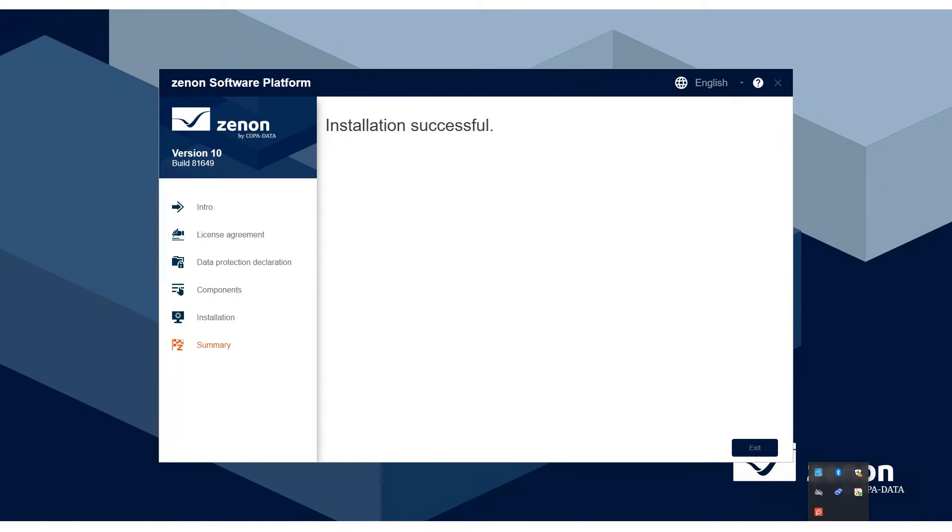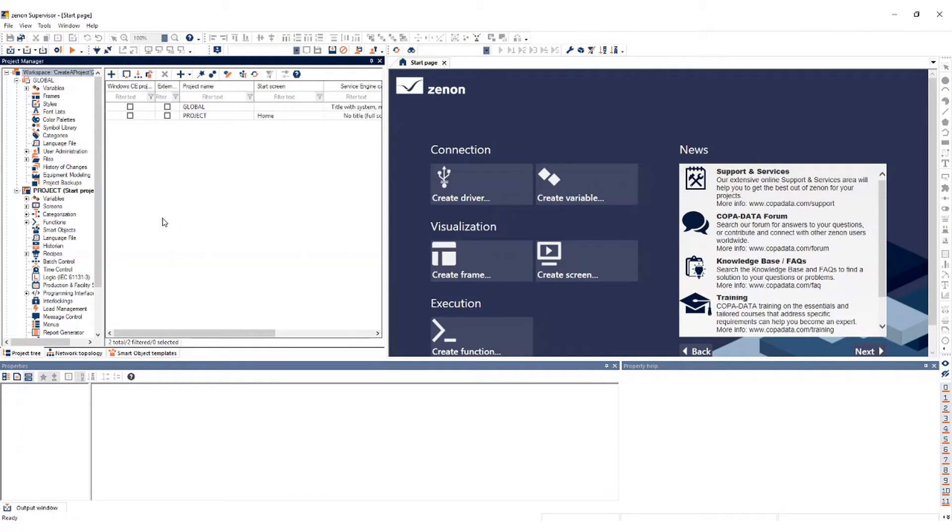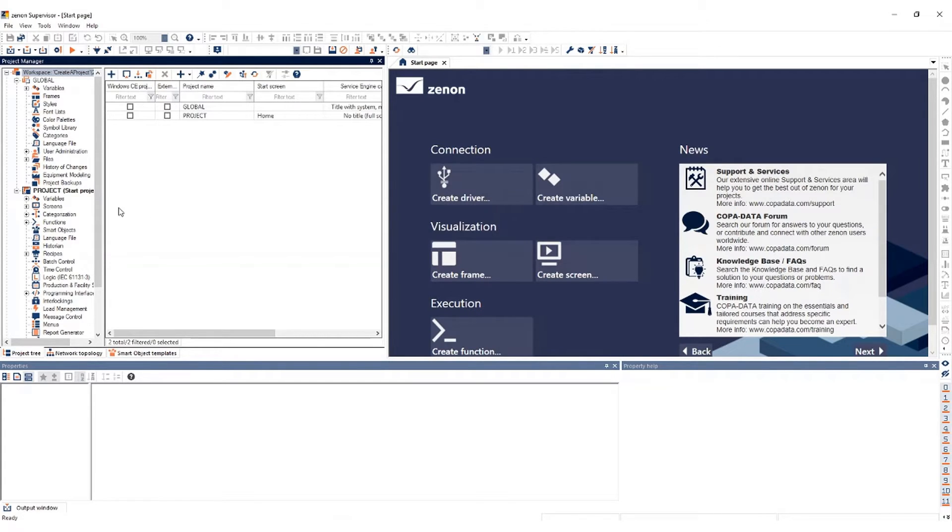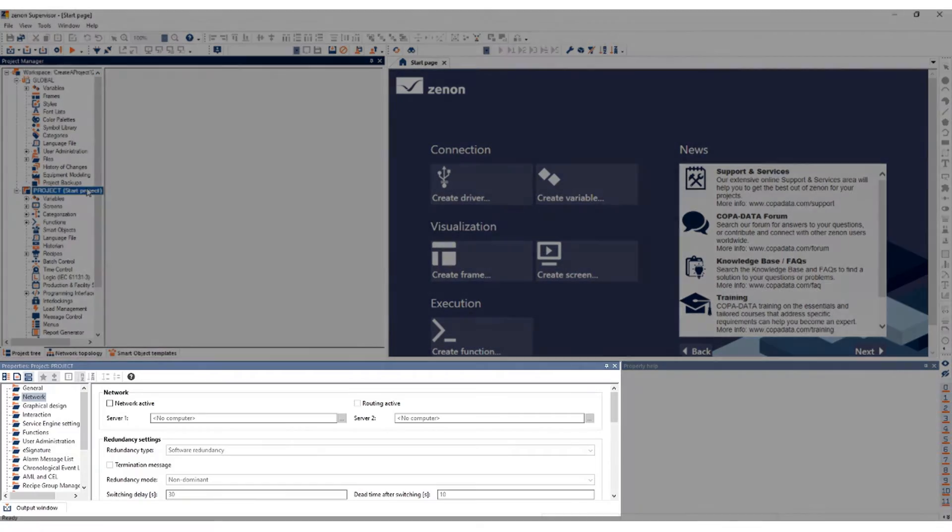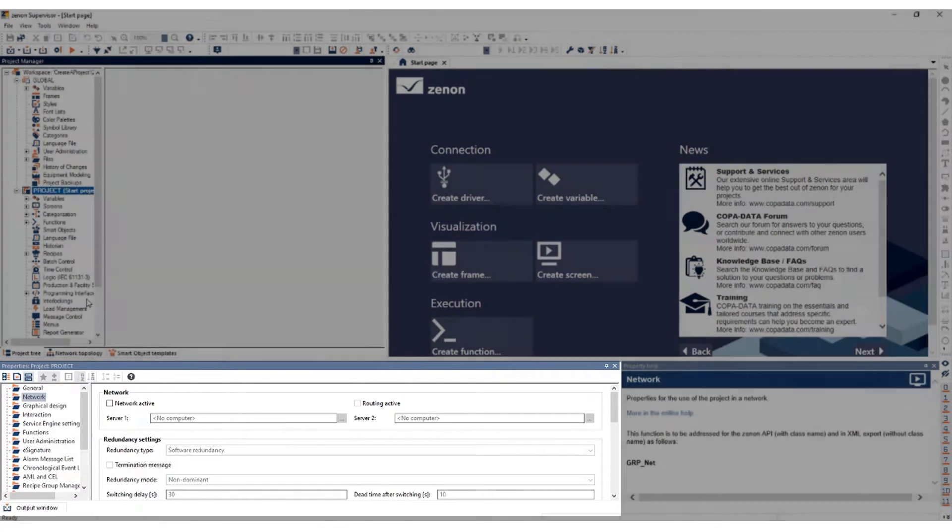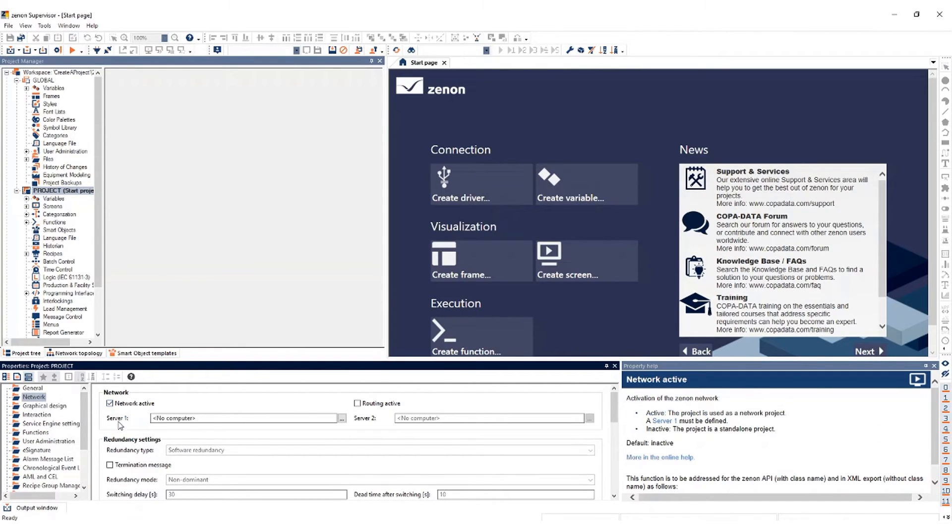Now that it is completed, the project can be configured to work on the web. In the Engineering Studio, open the project you would like to run on the Smart Server. Access its properties by selecting the project's name in the project tree. These properties will appear in a window at the bottom of the Engineering Studio. Navigate to the Network category and check the Network Active box.